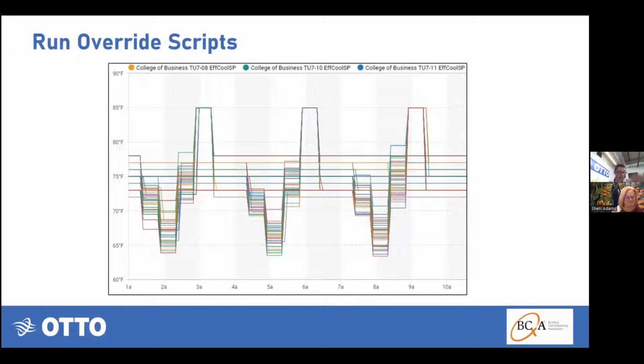Now again, this is not the controls contractor doing this. Because it's a BACnet control system, we are on the network utilizing our gateway, and we are able to make these simple overrides on your behalf to mimic your test script.